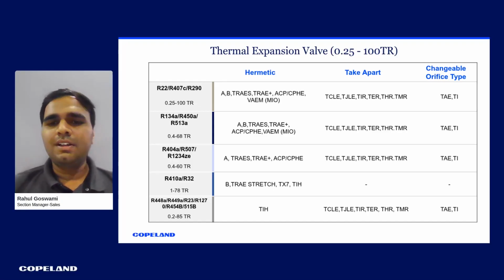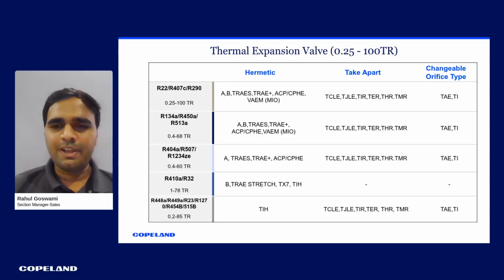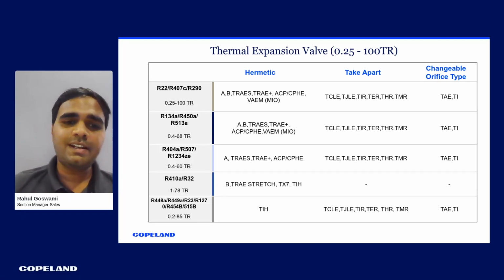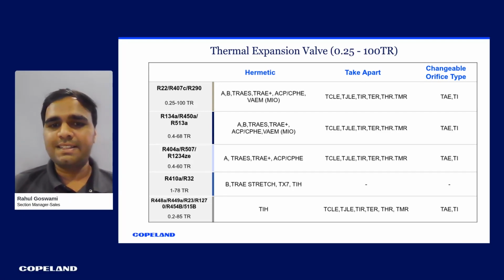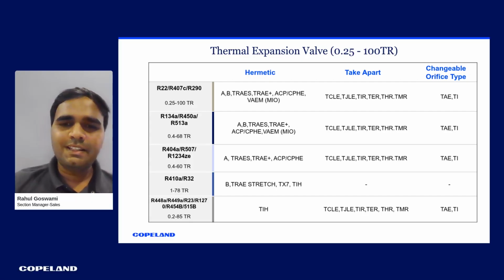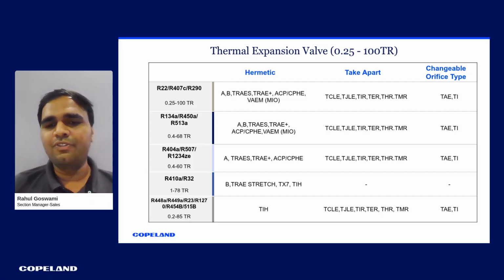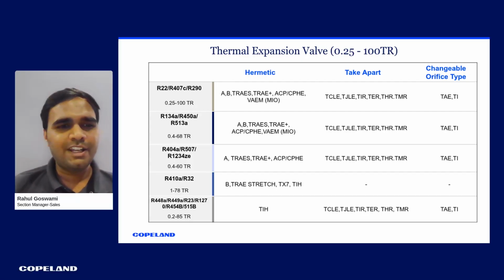So the first product is thermal expansion valve. In thermal expansion valve, we have a solution up till the 100 TR capacity. There are basically three types of thermal expansion valve which we have. First is hermetic expansion valve. In hermetic expansion valve, basically the whole expansion valve is welded.